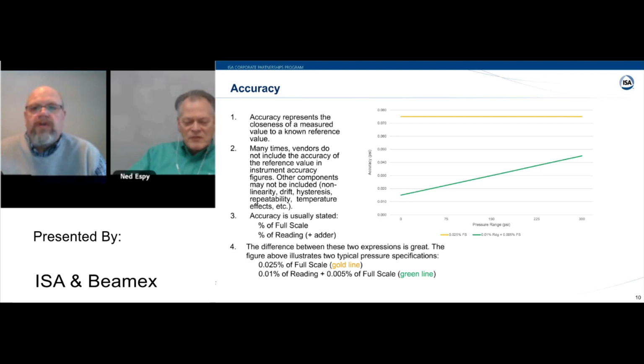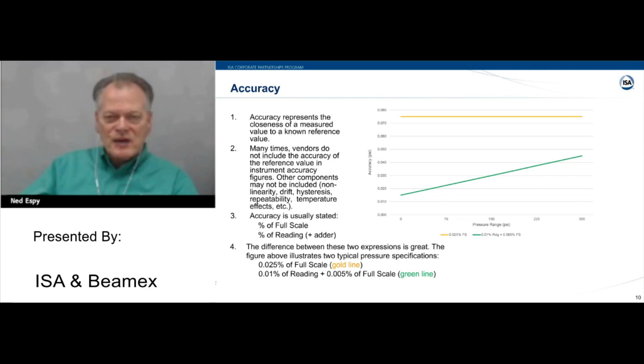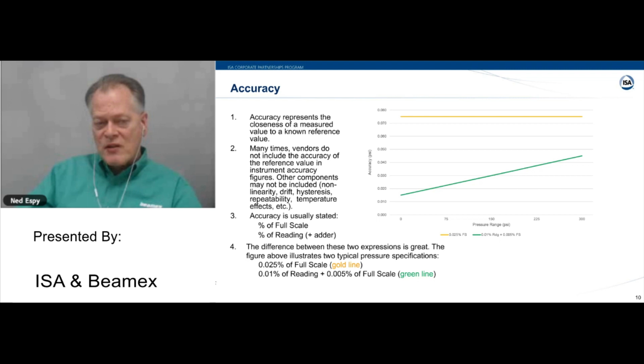Yeah, great point, Rich. And so when you're trying, as Rich says, to do some analysis, an apples to apples comparison, here's an example. What if you see something that's a percent of full scale, but on another device it's a percent of reading, and maybe there's some fixed component involved in that. So these are typical or common ways to state accuracy.